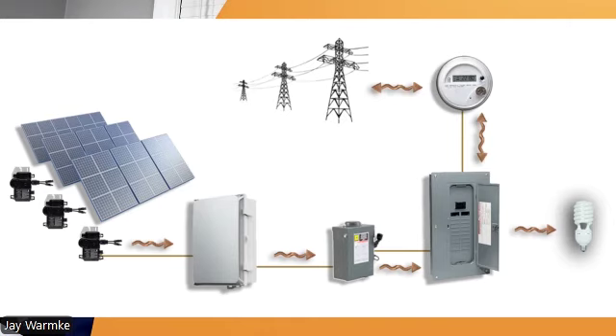So we've got these microinverters. They go to, in this system, this is an Enphase system, it goes to a combiner box. That combiner box is there for larger systems where you can hook up to 4 branch circuits, and you can have up to, with the IQ8 Plus, you can have up to 13 panels in a branch circuit. So this system would accommodate up to 52 panels. But the other thing that's in that combiner box is the communication system. So if you want to monitor the output of your panels, it's got to have that combiner box. You've got to have something that it's going to then take the data of what it's producing and feed it through the internet to your phone. And then it has an AC disconnect, and then you hook into your service panel again, and it goes to your loads, and it goes to the grid, and everything goes back and forth.